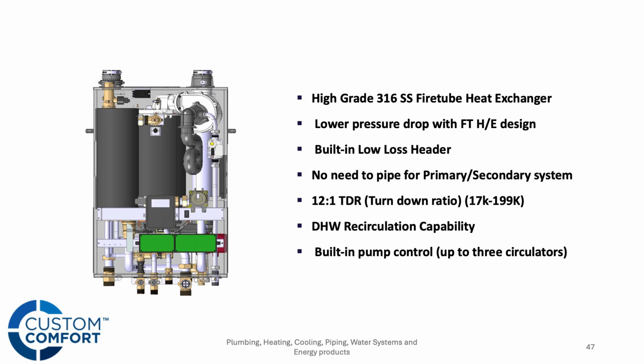But the other benefit that comes from that is the lack of need for primary and secondary piping. Because of the water content in the volume between the fire tube heat exchanger and the low loss header, it's just under 4 gallons of hydronic water at that point. There's enough volume there where we don't need to pipe this thing primary or secondary, right?